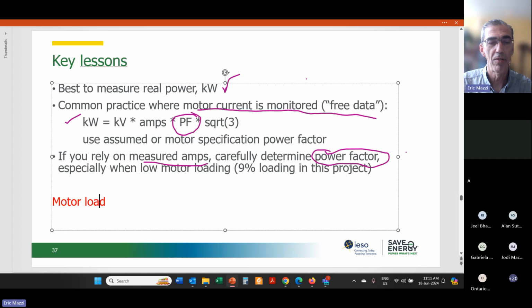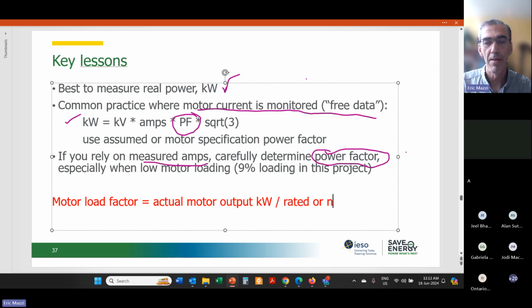Yeah, so motor load factor is equal to actual motor output power, or let's call it kW, divided by rated or nameplate output kW. So that's what motor load factor is. In this case, that ratio was about 9%, which I estimated based on some real power ratio. I could take more time to explain that, but I estimated the actual motor load factor using the real power ratio, and I believe that's where I came up with the roughly 9%.